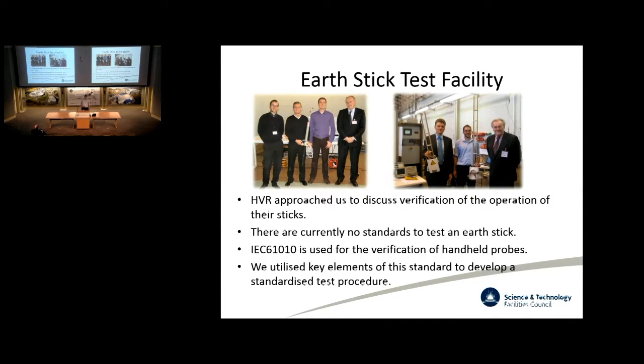It's the earth stick test facility. The first question you probably have is, what is an earth stick? Those big things there are what people call earth sticks. We use them as a safety measure for discharging potentially live high voltage equipment, so anything that could store a reasonable amount of energy, anything bigger than about 4 joules. We use an earth stick to make sure that all of the components are no longer charged when we need to work on them.